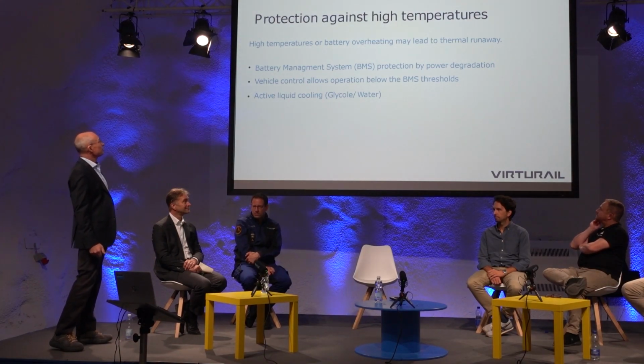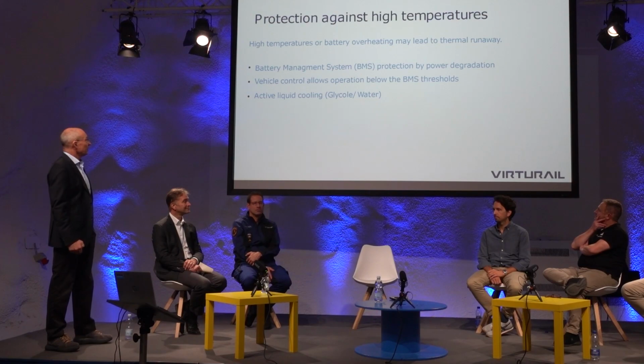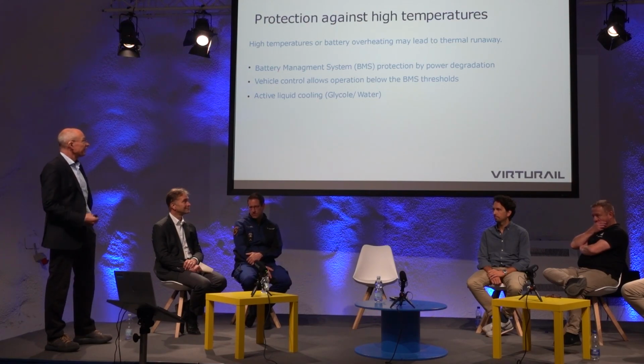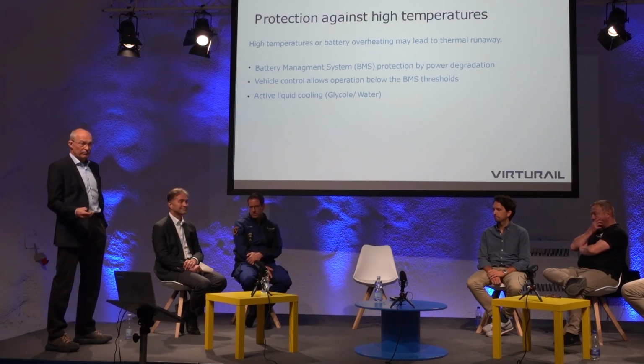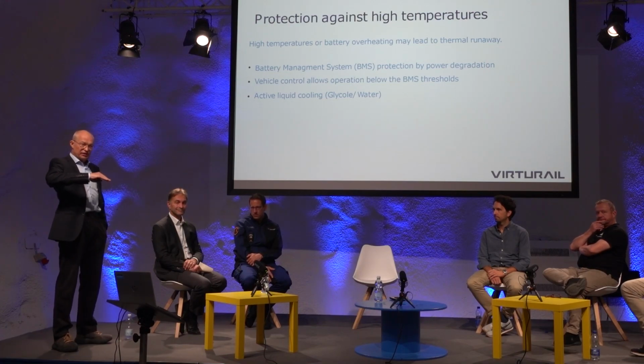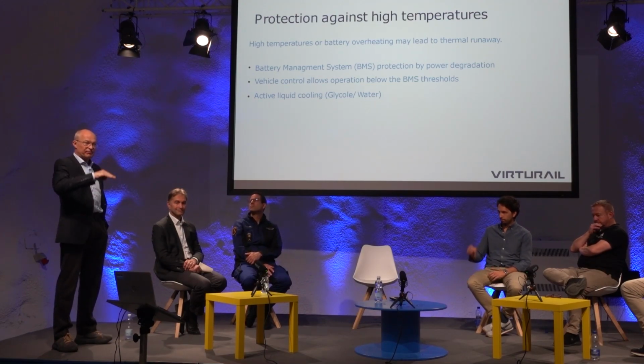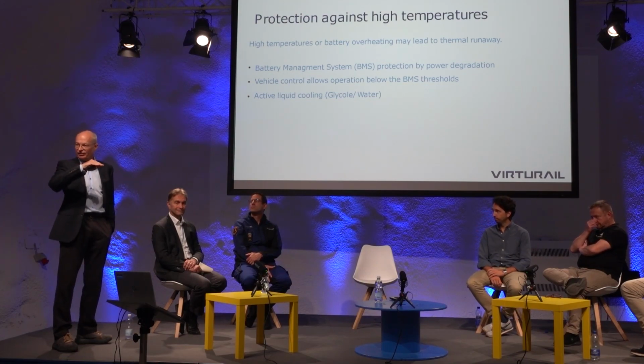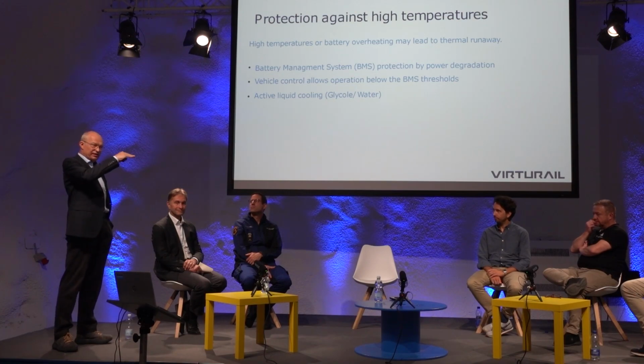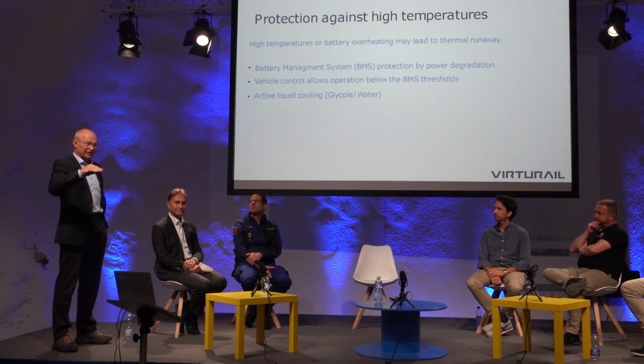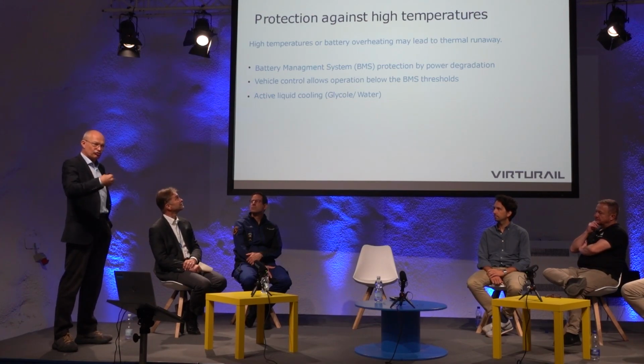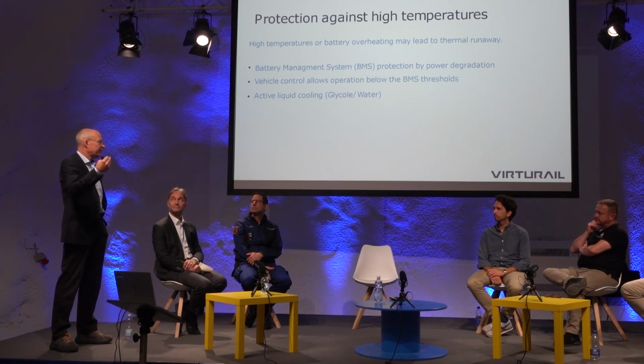The next topic is protection against high temperatures. First, the battery management system provides protection by degrading the power. As soon as the battery temperature rises above a certain threshold, depending on the kind of battery we are using, these thresholds may differ, but let's say at a temperature of 45 degrees centigrade, degradation of the allowed power starts to take effect. So at this point we cannot draw more power than, say, 30 kilowatts or whatever.